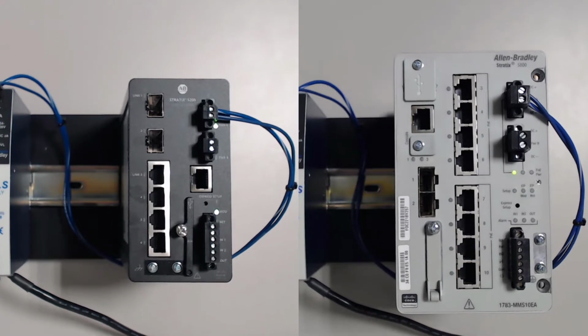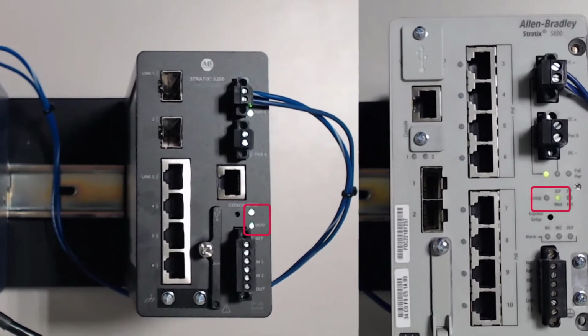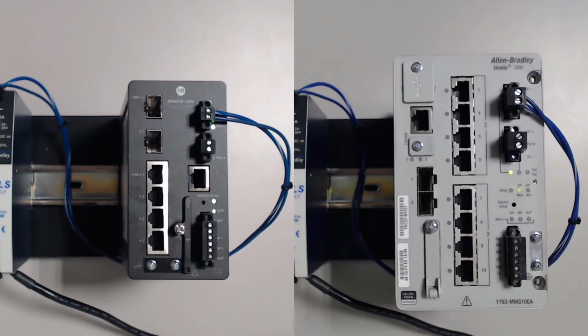Once the power on process has completed, the EIP mod and setup status indicators should be flashing green. Locate the Express Setup button. There are three Express Setup modes: Short Press, which takes care of initial setup with a default IP address; Medium Press, which also takes care of initial setup but uses a DHCP assigned IP address; and Long Press, which also resets the switch to a factory default state and is typically used when setting up a previously configured device. This video will focus on the short press mode, which requires a directly connected computer to complete the setup process.